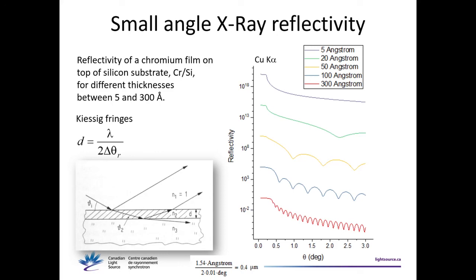This is a simulation of a chromium film on a silicon substrate with different thicknesses. The thicker the film, the more frequent the oscillations. Very thick films will have very frequent oscillations — delta-theta will be very small. So for reflectivity measurements you want very small divergence in your setup, because if you have a divergent beam you can make two-theta steps as small as you want but the oscillations will be washed out by your beam divergence.